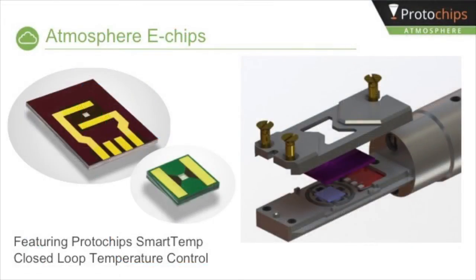The patented Atmosphere e-chip devices are a core component of the Atmosphere system. An e-chip pair creates the environmental cell inside the holder tip. One e-chip features an amorphous silicon nitride window, and the second features a proprietary ceramic membrane, which serves as both a sample support and heat source. The silicon nitride window is electron-transparent and provides a strong barrier to reliably contain gases up to one atmosphere for extended periods. The Atmosphere software controls the thermal e-chip device and uses Protochips' SmartTemp closed-loop control to automatically compensate for gas type or pressure.